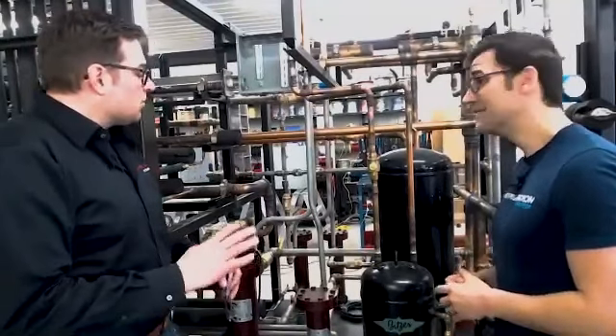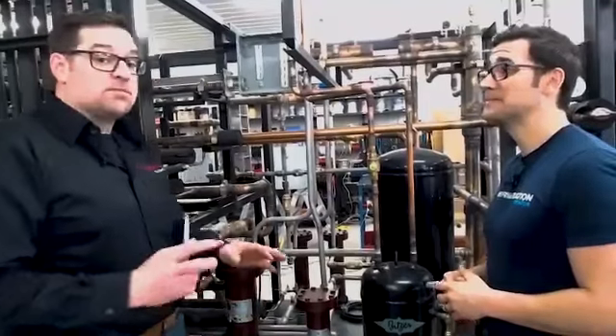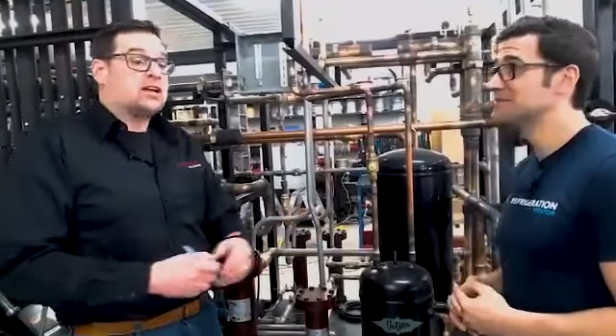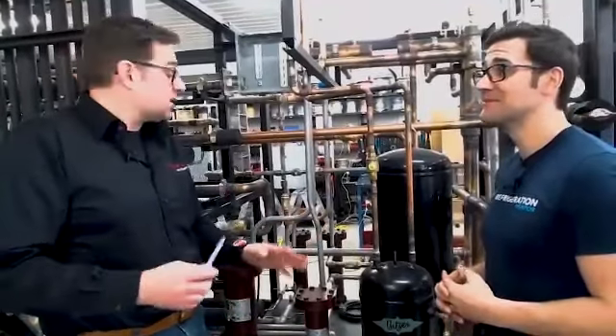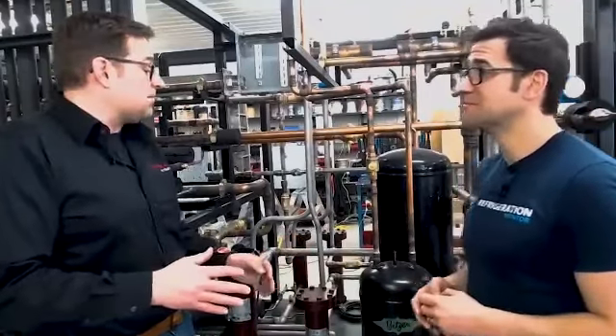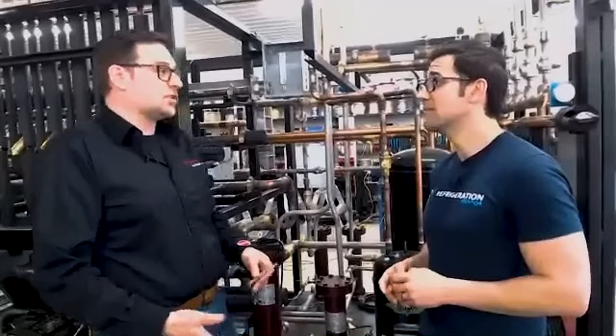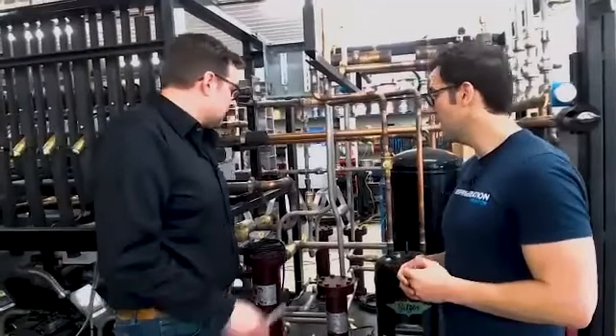Moving towards that, oil flows much easier because the pressure differential is so great. Make sure the type of compressors you're working with can handle a high pressure oil design. Working with something like Copeland scrolls may not be the best application for a low temperature, high pressure oil design, due to the limitations.